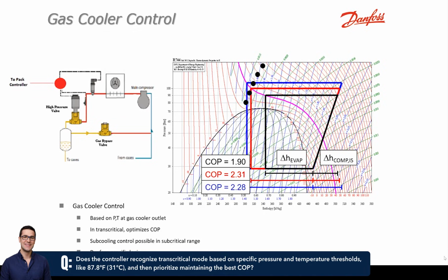Yep. And at this point, I know that on some manufacturers, they'll have an ambient probe as well. On this one here, it doesn't take that ambient probe into consideration, like on your other controllers, like your pack controller. Yeah, and the pack controllers aren't using that ambient temperature as part of the strategy for how these 2 valves would operate necessarily. Okay. That ambient probe really comes into play with the gas cooler fans and how they would be controlled.